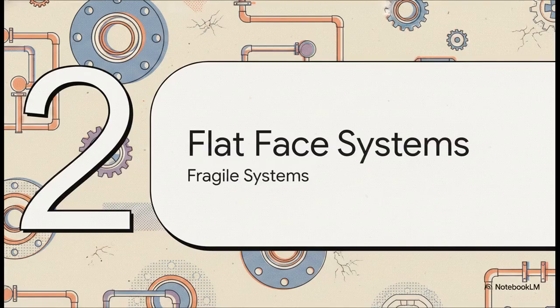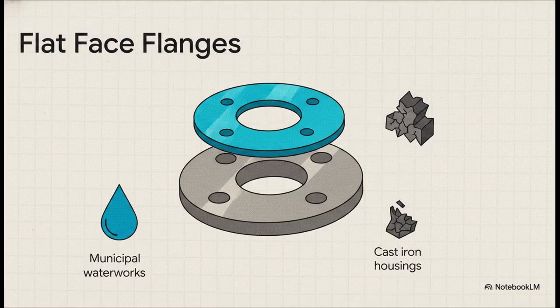Moving right along to Section 2, flat face, representing our fragile systems. So here we are at the lowest pressure rung on our severity scale. A flat face flange has its sealing surface on the exact same plane as the bolt circle. There's absolutely no raised section. You'll primarily find these used in low-pressure applications, like your standard Class 125 or 150 systems, municipal waterworks, and typical HVAC setups. And because the load is spread across the entire face, they require full-face soft elastomer gaskets. They're specifically designed to mate with more brittle equipment housings made of cast iron, fiberglass, or low-strength bronze.